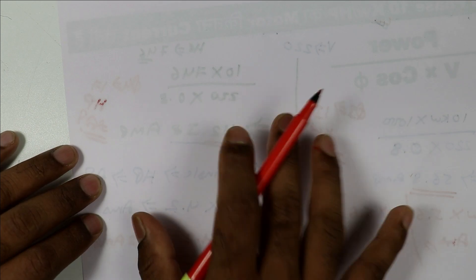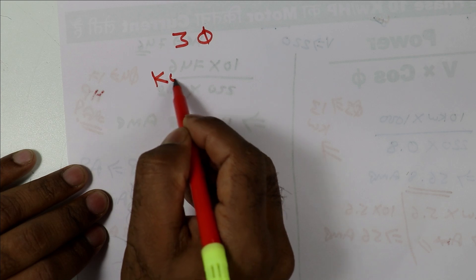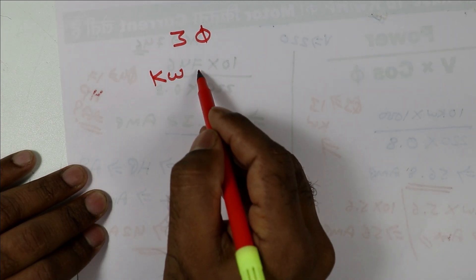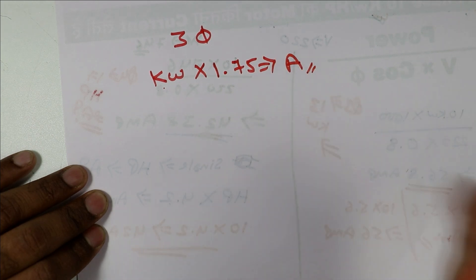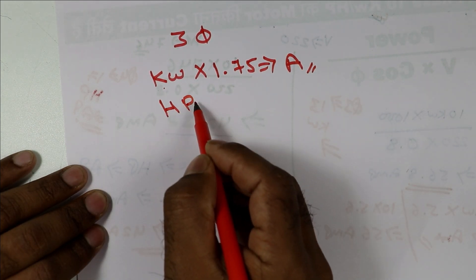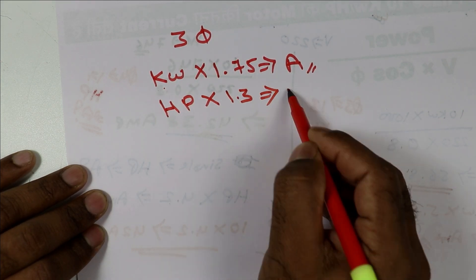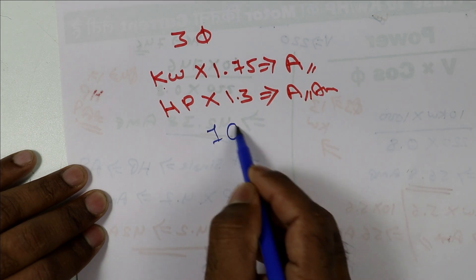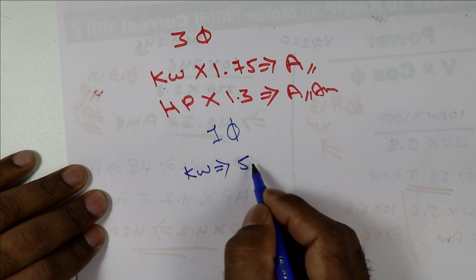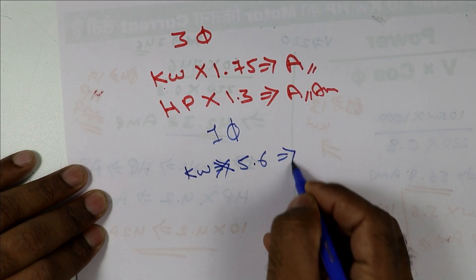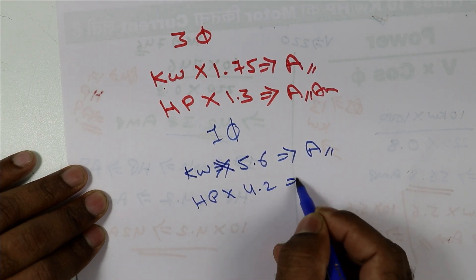Let us quickly recap all the short tricks. For a 3-phase motor with rating in kilowatt, multiply kW by 1.75. For a 3-phase motor in horsepower, multiply HP by 1.3. For a single-phase motor in kilowatt, multiply kW by 5.6. For a single-phase motor in horsepower, multiply HP by 4.2. Use these and you will get your answer in seconds.